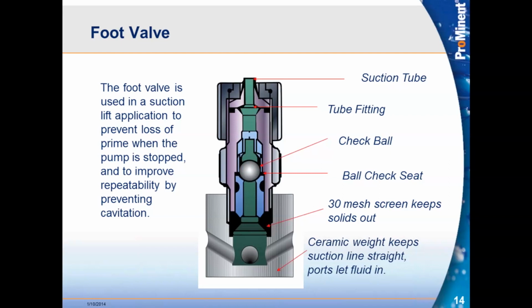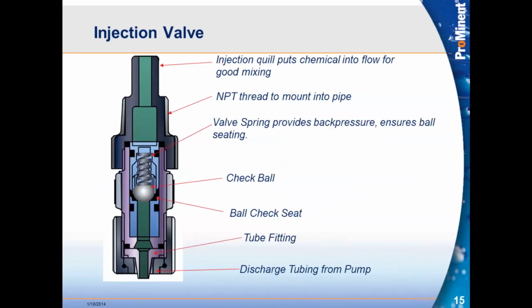It will etch that away, it will go away. So we have to replace that ceramic weight with, we have PVC weight to offer, and that's right in the catalog, right in the accessories section of the catalog. So we can easily supply that for you. The injection valve we talked about, it's a spring-loaded check, so we need a force again to open this to push the chemical past it. And that spring is fixed. It's providing about 7 psi of back pressure. We need 7 psi of force to open that to push the chemical past.